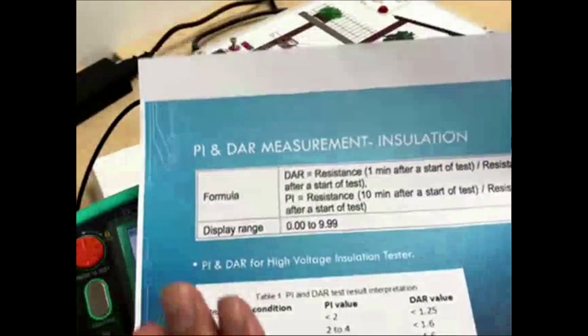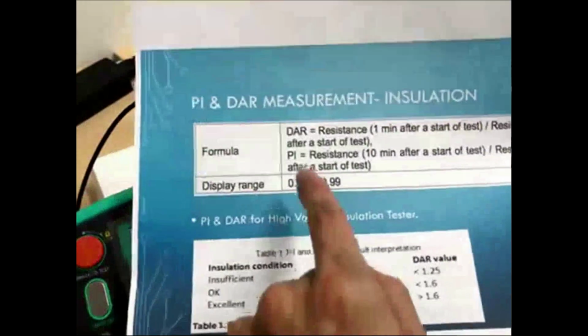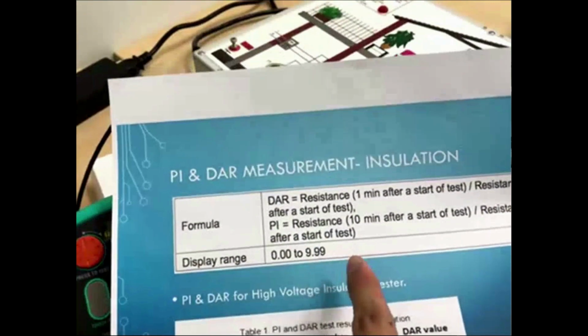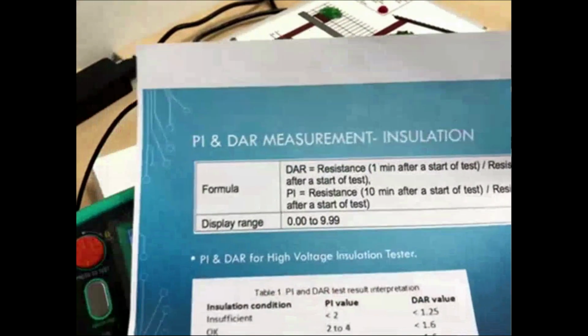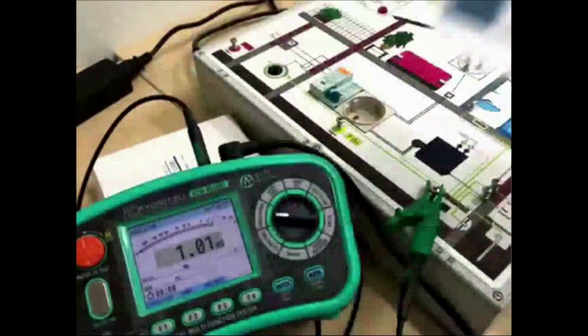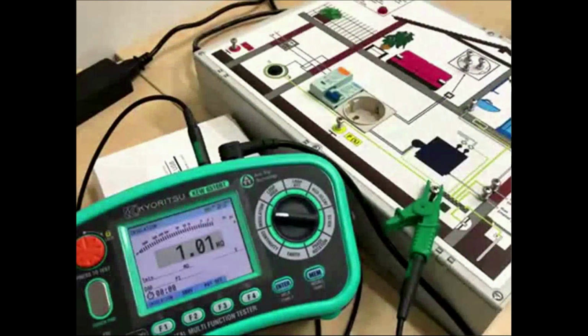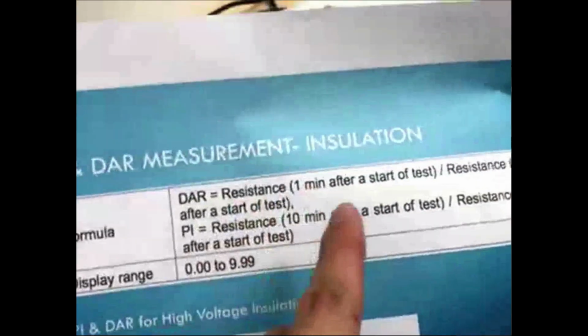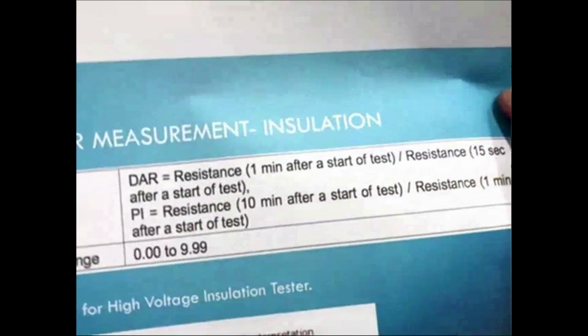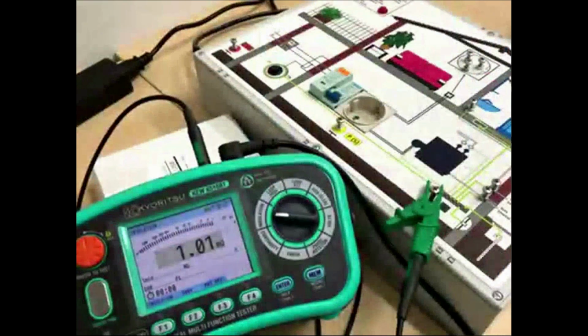In this test, I won't show you PI because it takes 10 minutes. Later you will skip it in my lesson. So I will try to show you DAR. So what is DAR value? DAR value, I repeat again. DAR value is 1 minute over 15 seconds. Okay, see what I test.